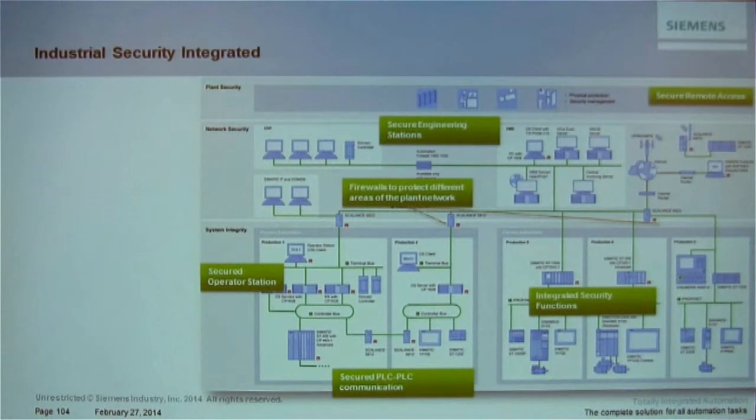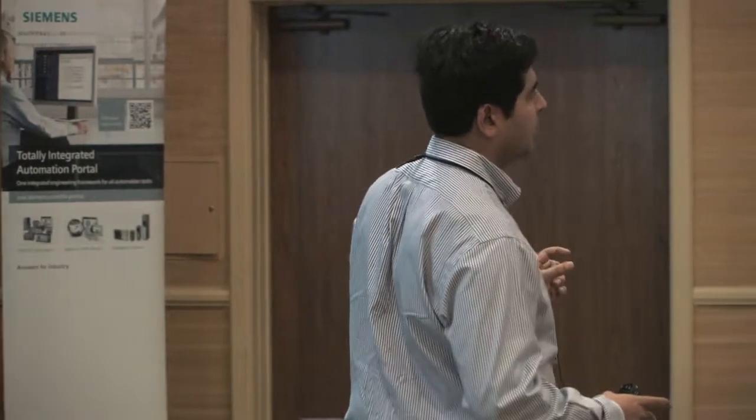That's a little media module. Say I need to configure an Ethernet switch. I assign an IP address, I set my ports, it's working fine. Now I go install it at my facility, and that machine ships to someplace else. It got my configuration on it. It was working fine when it left. Now guess what? This guy calls me and says, hey, I can't talk to it. Well, then I'm scratching my head going, has he changed the IP address? Has he changed the port settings? You know, what's going on? This little media module plug stores the configuration of that device locally.